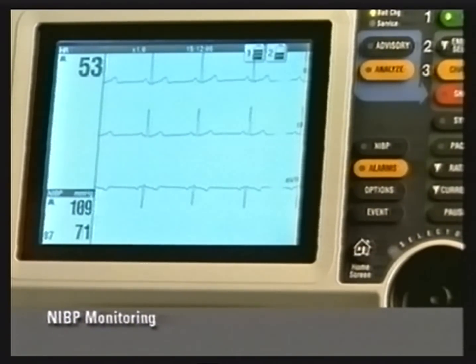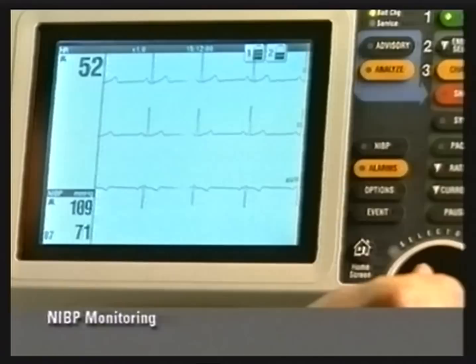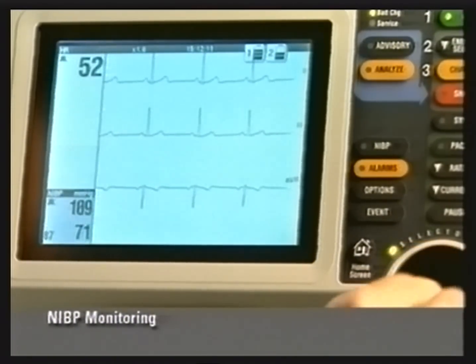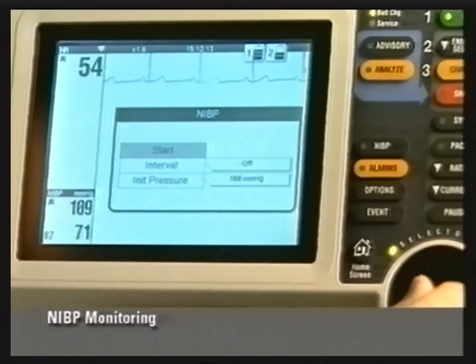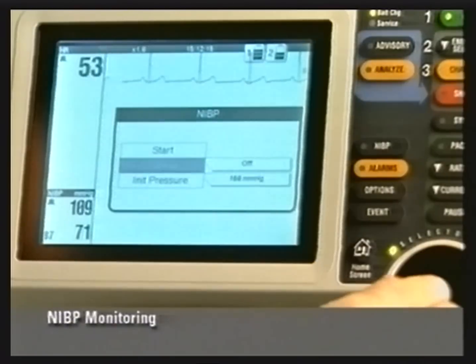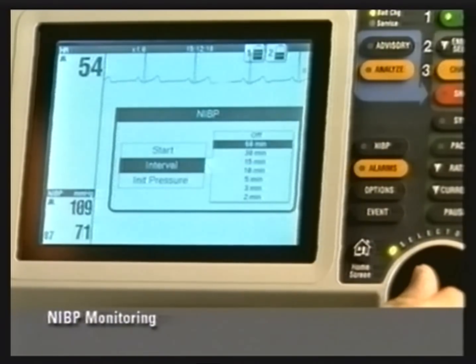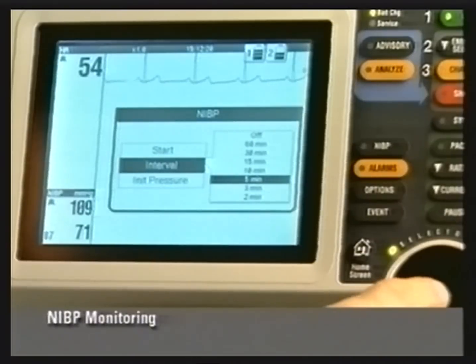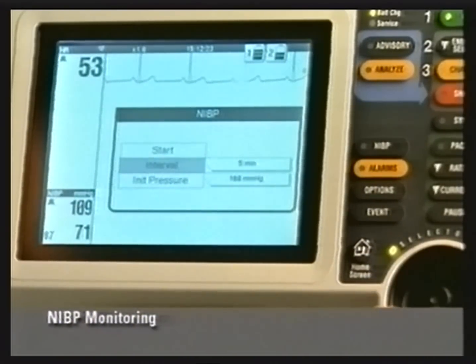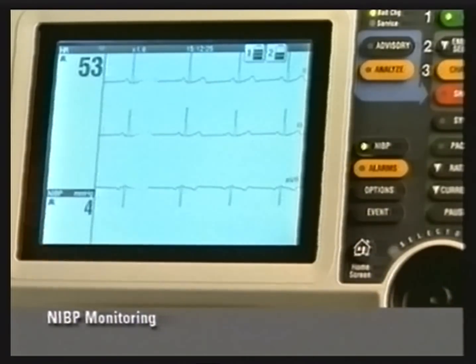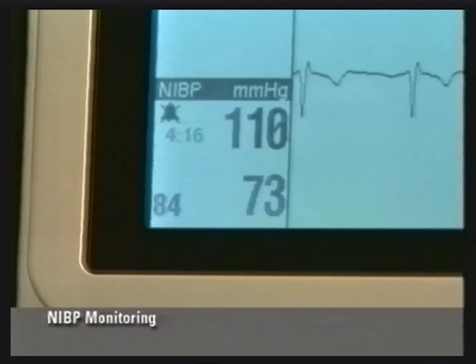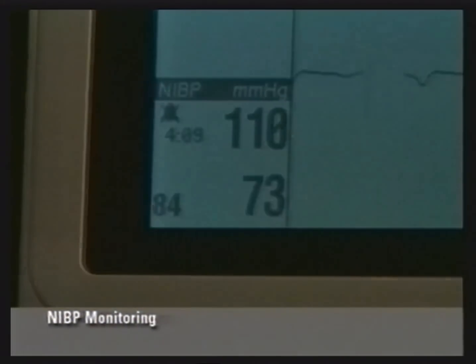To set an interval while monitoring a patient, use the selector to highlight and select the NIBP area. The NIBP overlay appears. Select interval. The available intervals are displayed from 2 to 60 minutes. Highlight the interval that is desired. Select Start or press NIBP to initiate a blood pressure measurement. After the blood pressure measurement is obtained, the timer is displayed next to the systolic pressure. The timer counts down, indicating the minutes remaining until the next NIBP measurement.